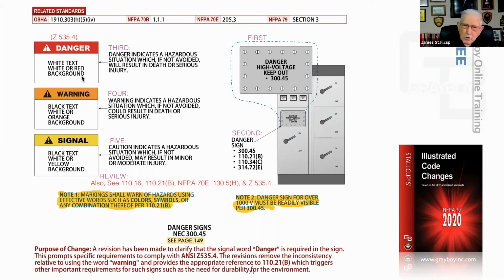But say you have a situation where you enter through the gate, and you have components over 1,000 volts that would be lower than the elevation required by IEEE National Electrical Safety Code chapter 1. Then you'd have a warning on the gate, but another fenced-in area around that equipment that had danger signs.